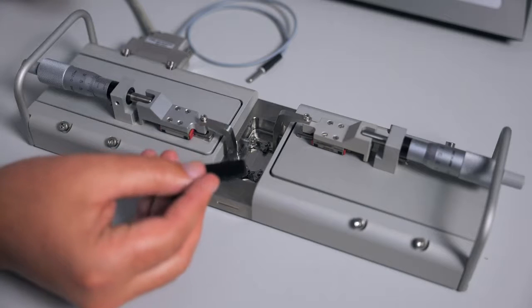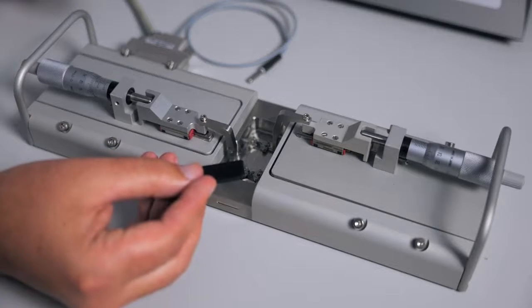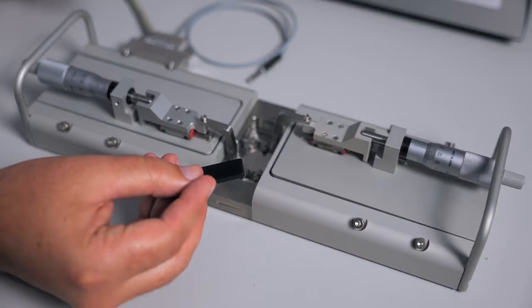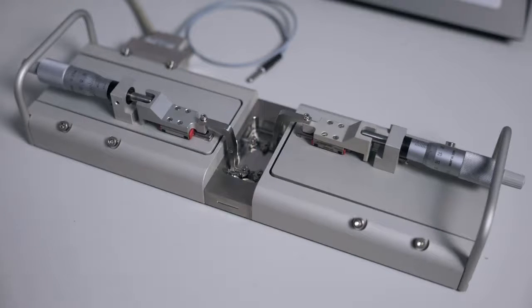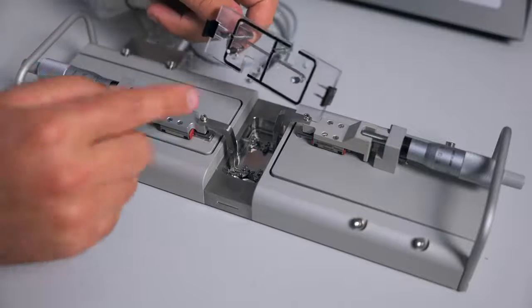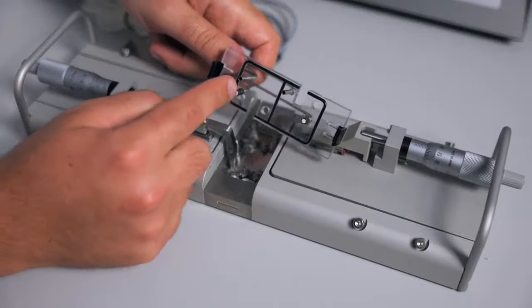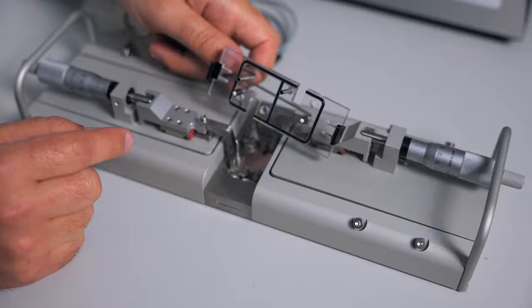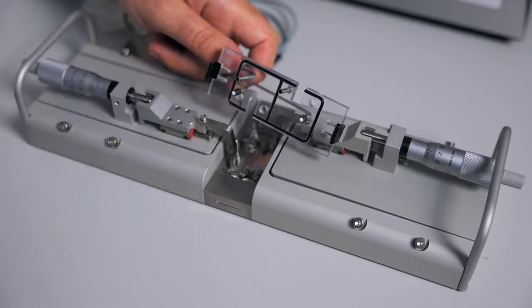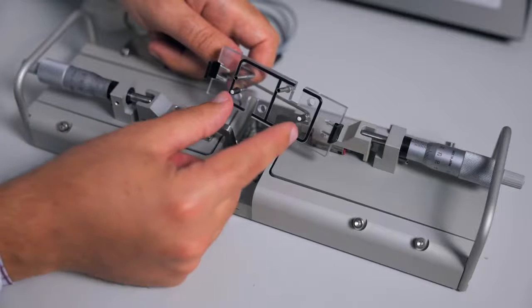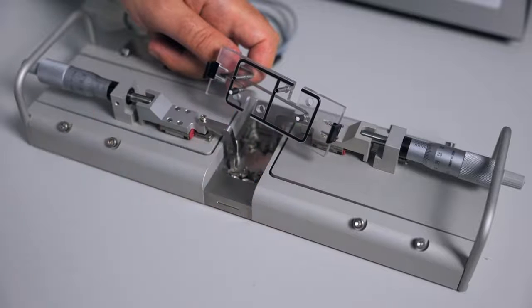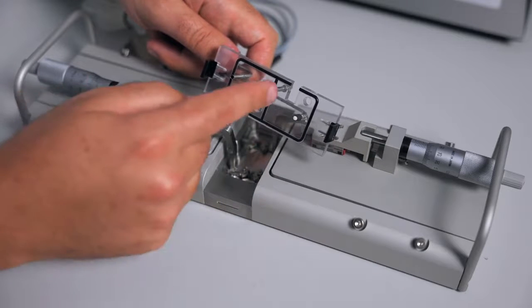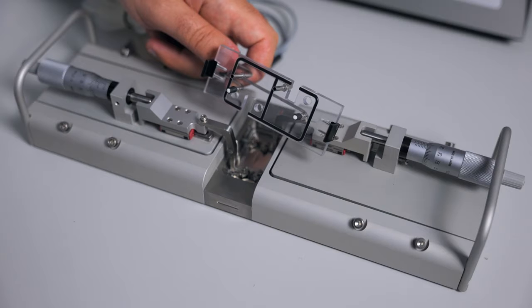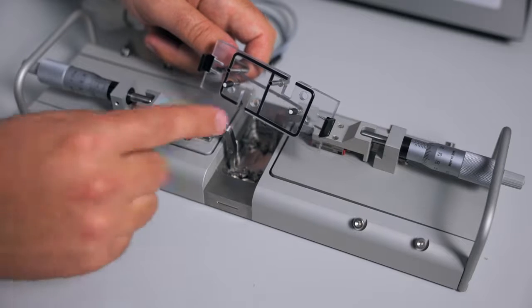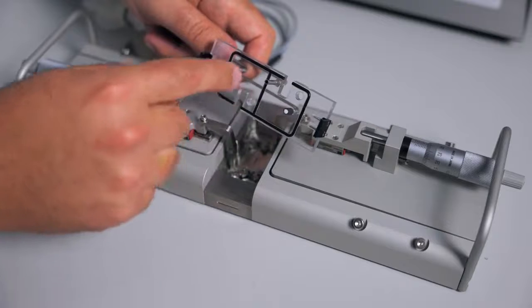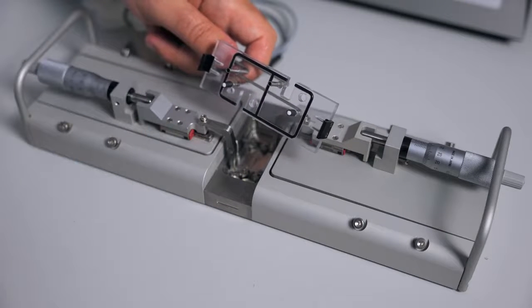You should also make sure to wash the chamber divider with acetic acid and water after you're done cleaning, as well as let the vacuum run for 10 seconds for the chamber cover to eliminate any buffer that's left in the pipes. Keep your oxygen bubbling on until you are done cleaning the chamber and running the vacuum for the cover. Wipe down any remaining buffer that you see on the chamber cover.